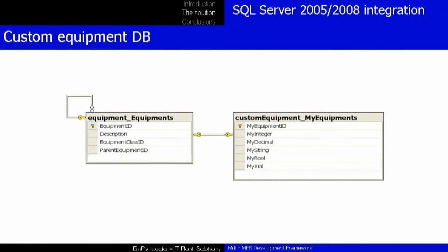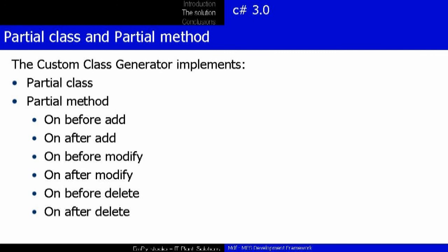As a last step, the custom class generator will create an entity model to ensure that a single entry point allows access to the storage layer. All this will be done using the Entity Framework that Microsoft released at the end of 2008. All the entities have the characteristics of the ISA-95 standard and attributes defined by the user developer. All classes generated by the custom class generator are partial classes and expose several partial methods. Using this technique, introduced by Microsoft with C# 3.0, it will be possible to add custom properties and custom methods, as well as add special control during the add, modify, and delete operations. All this code can be stored in separate files, so the custom class generator will not overwrite them.